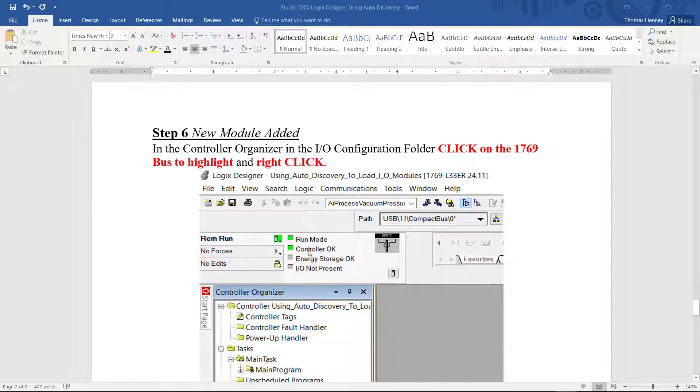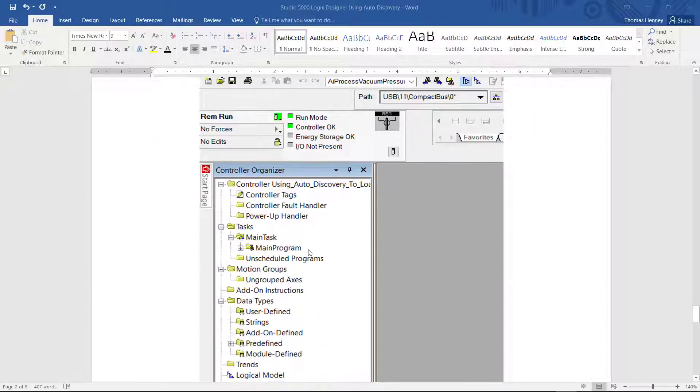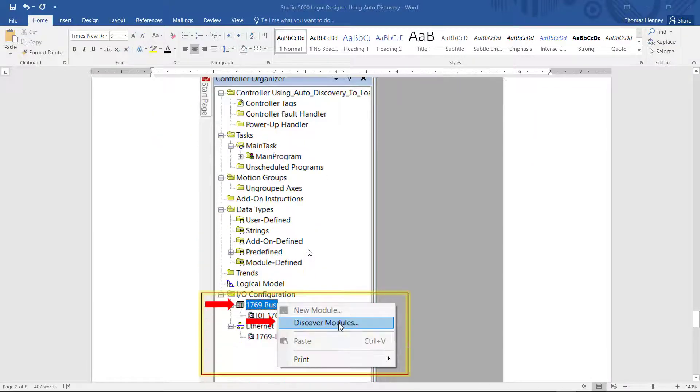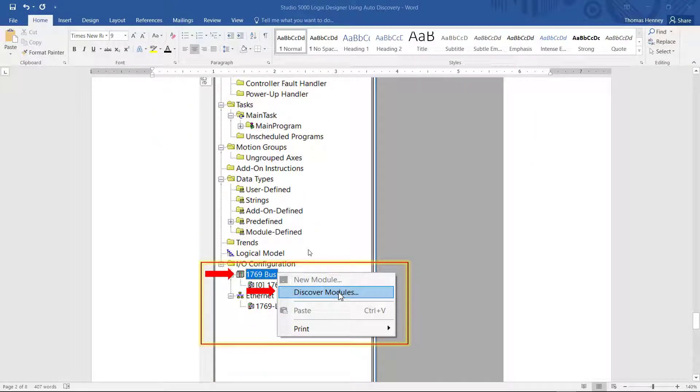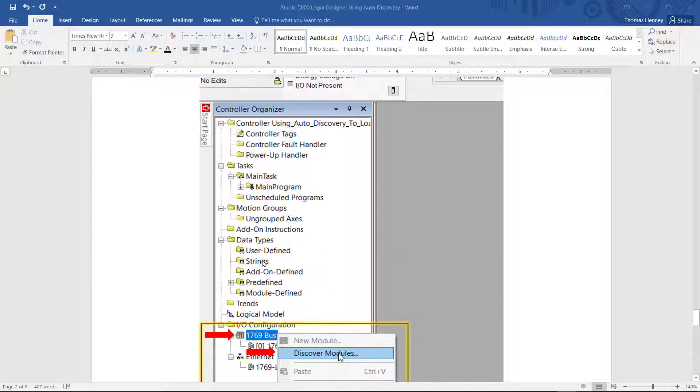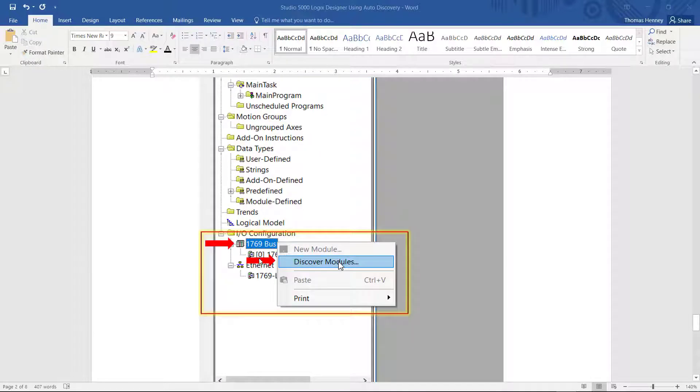In step six I'm showing how to use the auto discovery feature. And you will come down in the controller organizer down to the 1769 bus. Right click and click on discover modules.